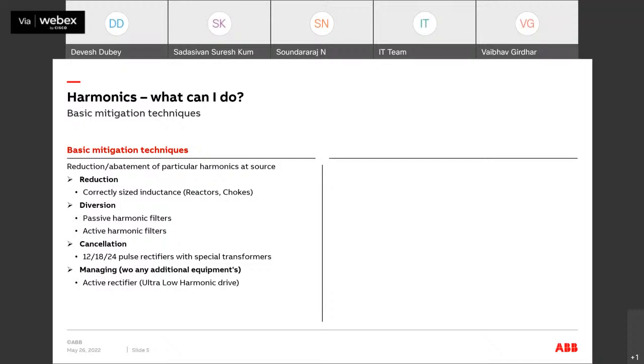We have different methods by which we can have a reduction. We can introduce reactors and chokes correctly sized with the inductance. We can divert the harmonics by using passive and active harmonic filters. We can have a cancellation effect by having 12 pulse, 18 pulse, or 24 pulse converters or rectifiers with special transformers. The best way, which we are going to talk about today, is an active rectifier or active converter, which we also call ultra low harmonic drives.